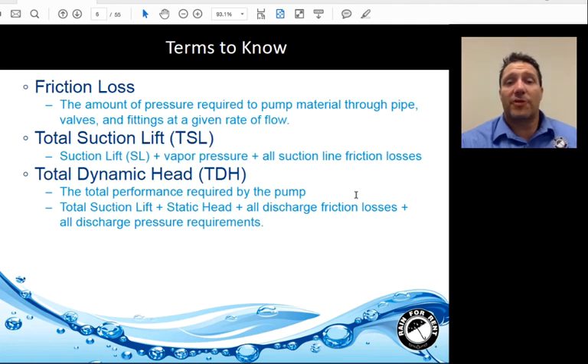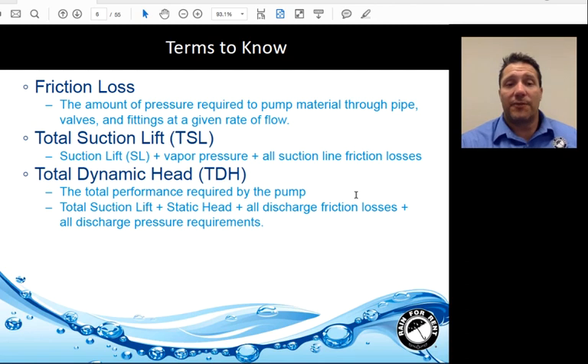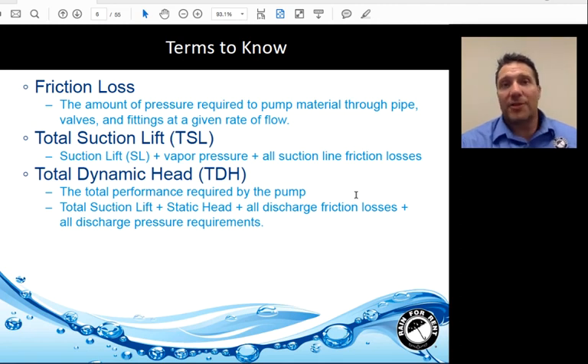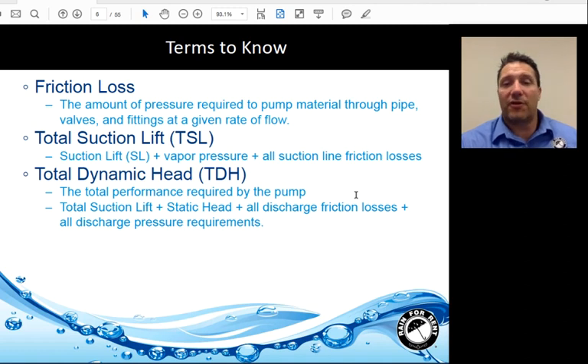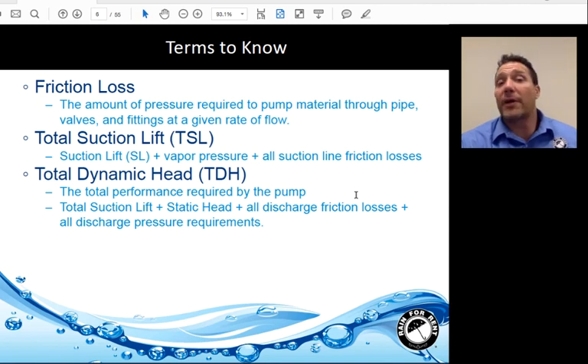Friction loss is the amount of pressure required to pump material through piping, valves, fittings, hose, etc., at a given rate of flow. Total suction lift is the static suction lift, plus the vapor pressure, plus all suction line friction losses. Total dynamic head (TDH) is the total performance required by the pump — it is total suction lift, plus static head, plus all discharge friction losses, plus all discharge pressure requirements. An example of a discharge pressure requirement would be pumping into a force main or pumping into a tank.